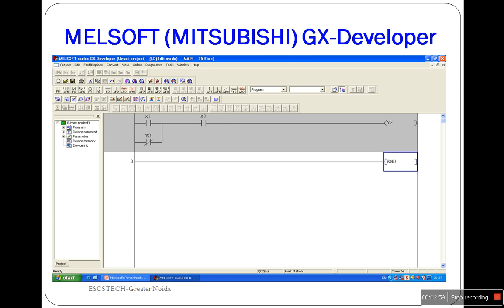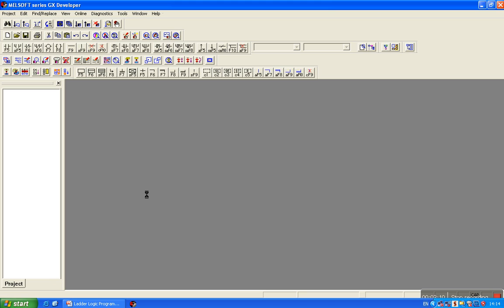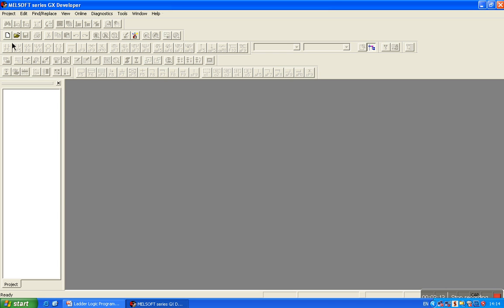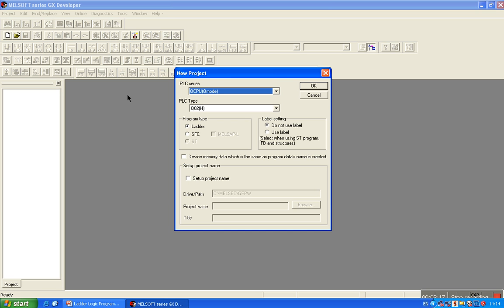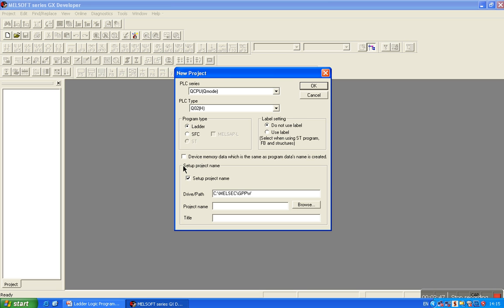Now let us learn the procedure of programming with GX Developer. Open GX Developer and click on New Project. Select the PLC on which you want to work, then select the PLC type. I am going to work on the Q02H type PLC, so I select QCPU (Q mode) and PLC type Q02H. The programming type is Ladder. You can make a directory for the project with a name, title, and path where you want to save it. I am not going to save any project, so I will leave it.